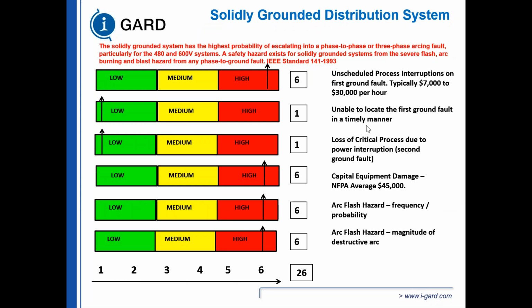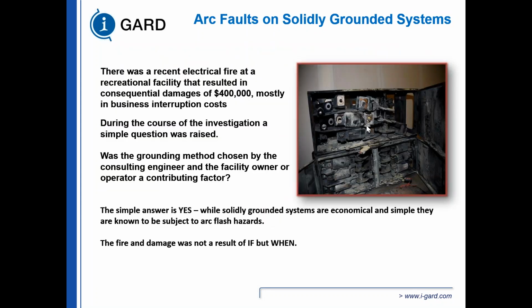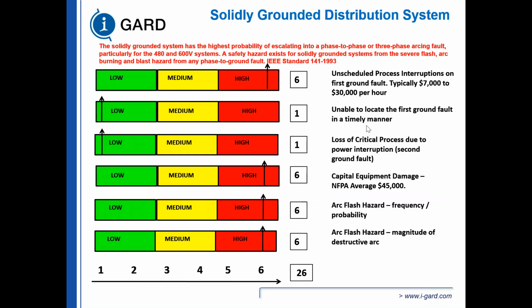Capital equipment is high. Arc flash energy is quite high. You can imagine the destructive nature that caused this kind of damage. And arc flash hazard was very high. So a solidly grounded system was 26 on the safety risk meter.